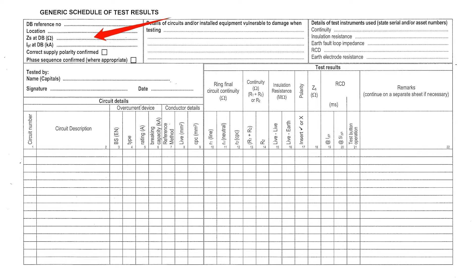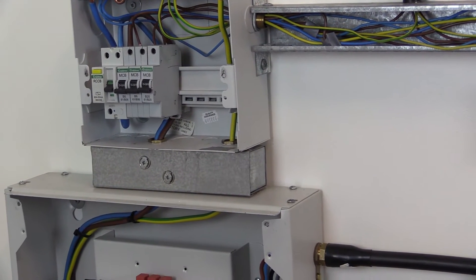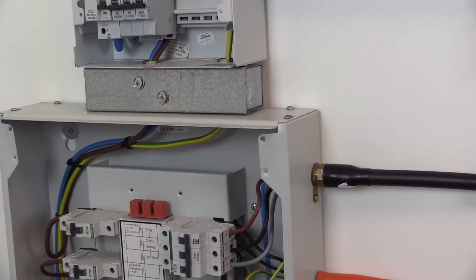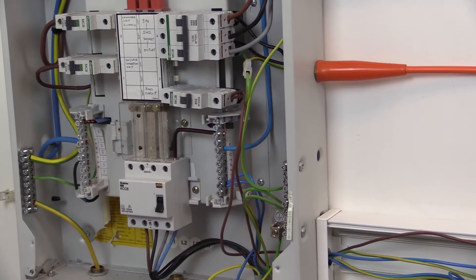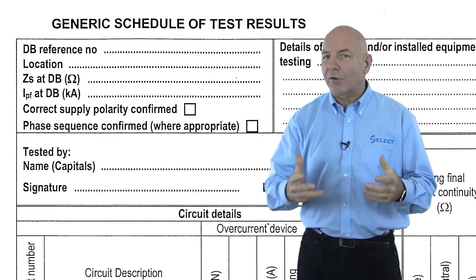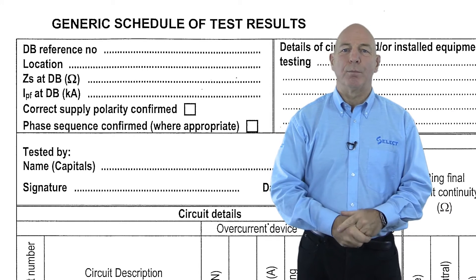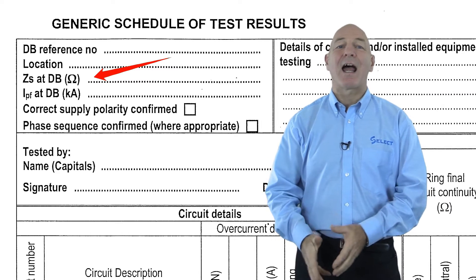The three values measured should be noted, and it is the highest value obtained that will be recorded as the earth fault loop impedance at the DB, recorded in ohms in the top left-hand side of the schedule of test results. On larger installations, the earth fault loop impedance external to the installation may not be at the incoming supply of the distribution board being worked on, as the actual incoming supply to the building may be located remote from this distribution board. The external earth fault loop impedance measured at the distribution board in this situation is therefore referred to as the ZS at DB.